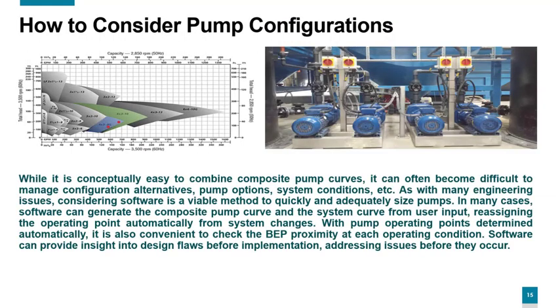Now, how to consider pump configurations? While it is conceptually easy to combine composite pump curves, it can often become difficult to manage configuration alternatives, pump options, system conditions, etc. As with many engineering issues, considering software is a viable method to quickly and adequately size pumps. In many cases, software can generate the composite pump curve and the system curve from user input, reassigning the operating point automatically from system changes. With pump operating points determined automatically, it is also convenient to check the best efficiency point proximity at each operating condition. Software can provide insight into design flaws before implementation, addressing issues before they occur.